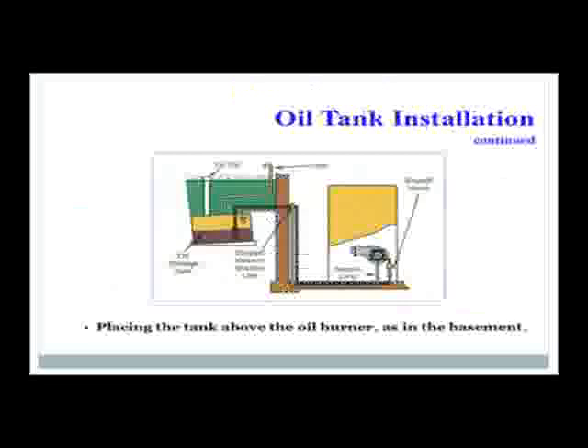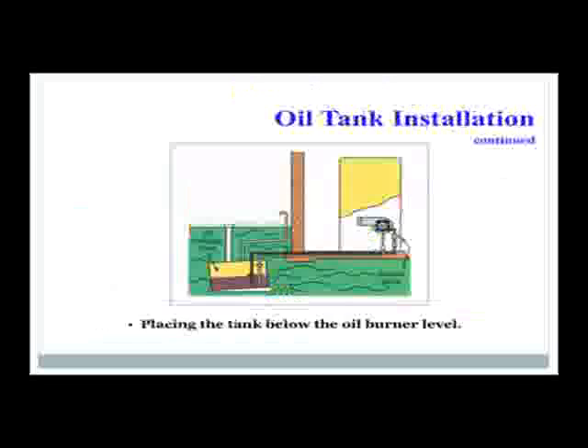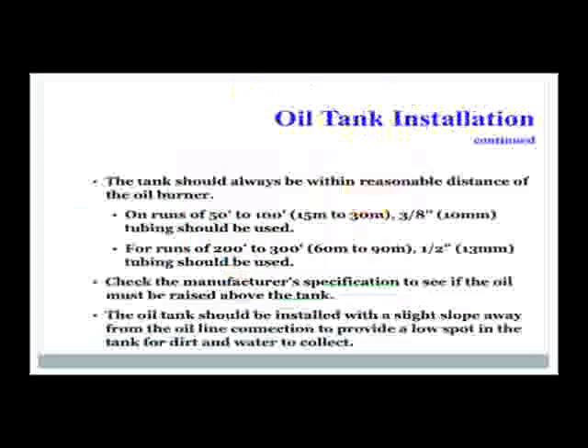Placing the tank above the oil burner, as in the basement, as in this picture, or below the oil burner, as in an outside oil tank without a basement. The oil tank should always be within reasonable distance of the oil burner. On runs of 50 to 100 feet, 3/8 inch tubing should be used. For runs of 200 to 300 feet, we need to go up to 1/2 inch tubing. Check the manufacturer specifications to see if the oil must be raised above the tank.